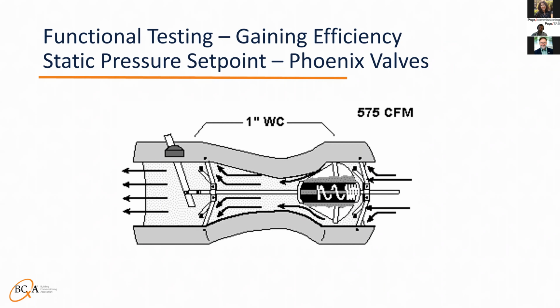And just as a side note, Phoenix actually sells static pressure reset kits for the valves, which is basically a differential pressure sensor installed on each valve. I think the valves should just come with them in this day and age, but if you can get away with charging extra, why not? And that information is really for design reviews. If you see those Phoenix valves submitted in submittal reviews without those static pressure reset kits, and you're supposed to have static pressure reset in your sequence, it's worth making a note.